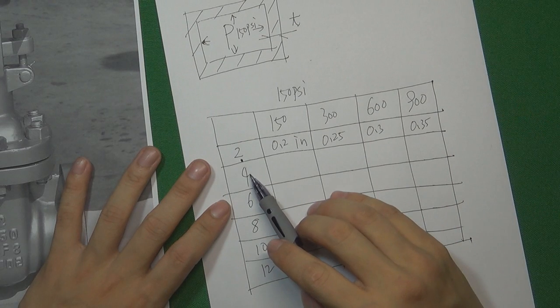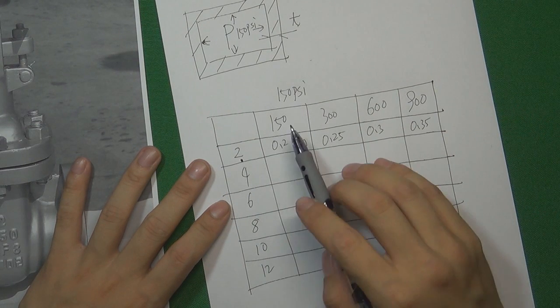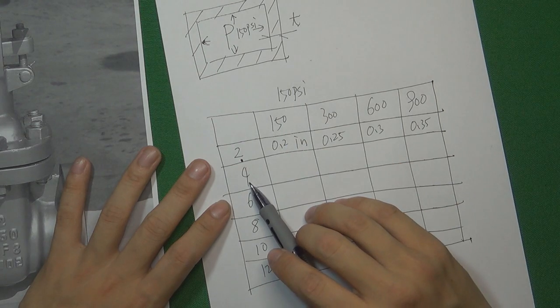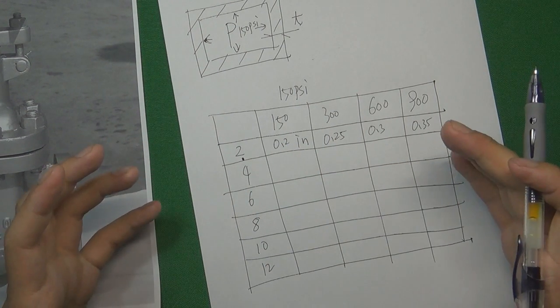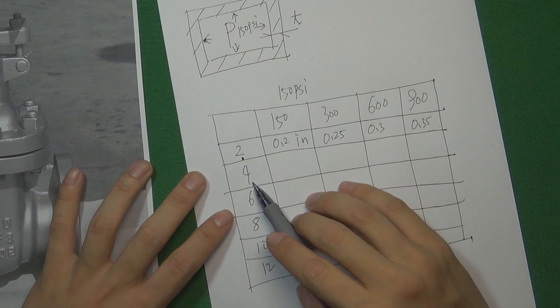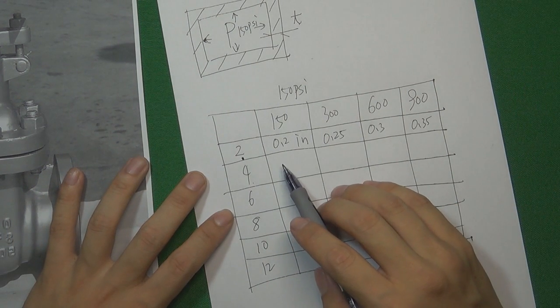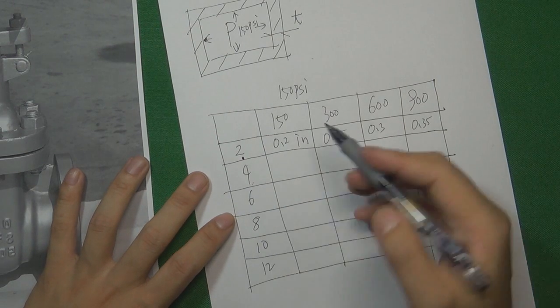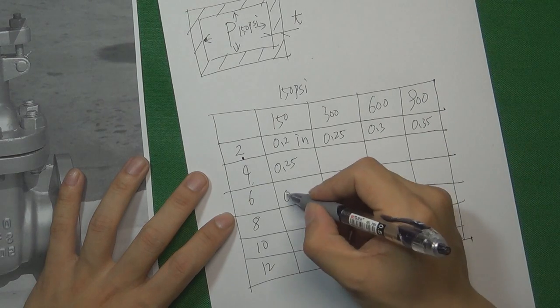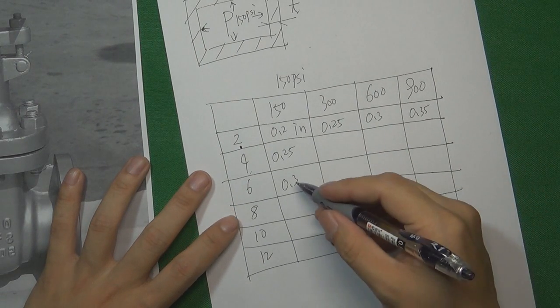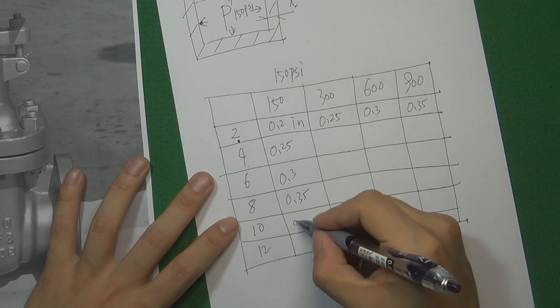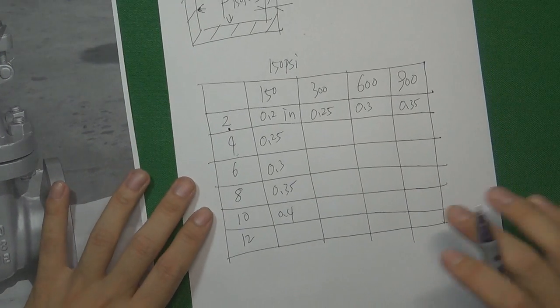Also, when the size is getting bigger, even though the pressure is the same, the bigger size will weaken the body. So with the size getting bigger, we need a thicker wall to hold the same pressure. For example, a 4-inch valve may need 0.25 inch; 6 inch maybe 0.3; 8 inch needs 0.35; 10 inch maybe 0.4. That is just an example.